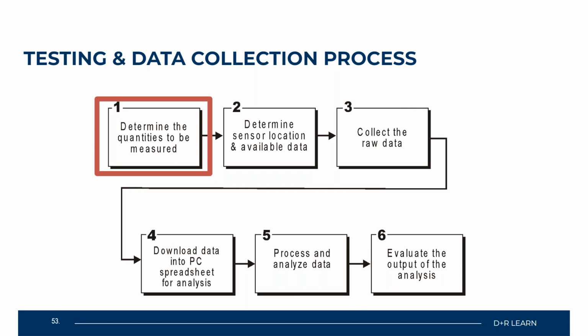And if you have the historical information to provide, especially to utility companies, it makes their job easier to help you in evaluating, and not just them, but your technicians or the contractor that'll be called in order to remedy the issues. It gives them a point to start. So data collection is an extremely important process when dealing with these HVAC systems. And once again, if you are able to perform data collection, it will help you to create and have a very efficient process at your facility and or site, especially within your facilities team. If you make that something that is a requirement every single day, you will have a smooth and very clean running operation.